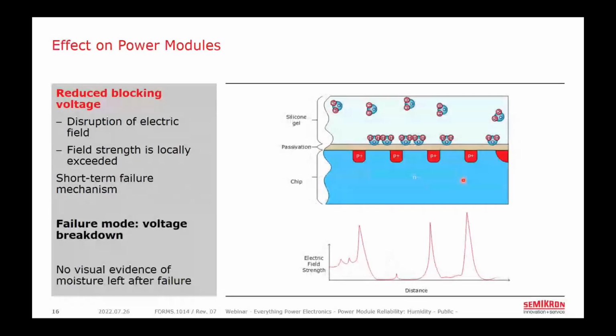But with high amounts of water molecules, either as vapor moving through the silicone gel near the chip edge or as outright condensation on the surface of the chip, this electric field can become disturbed. And if any one area has too high of an electric field strength, breakdown occurs and you'll have arcing there. The reason I'm differentiating between this failure mode and the earlier failure mode with corrosion is because this failure can occur anytime within an application, and oftentimes there's no evidence left behind. This is why it's really critical to understand the conditions that can cause high humidity to occur, and if there are failures, we need to consider the circumstances under which the failure occurred.